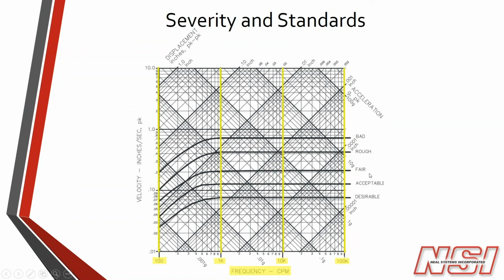So once you have a measurement of your vibration level, it might be helpful for you to consider a severity chart. You can find these from different suppliers. Metrix Vibration supplied this one. What these are used for is determining how severe your vibration is, and maybe this will help you to set your alarm levels at your facility based on some standards that are generally accepted across maybe your industry.